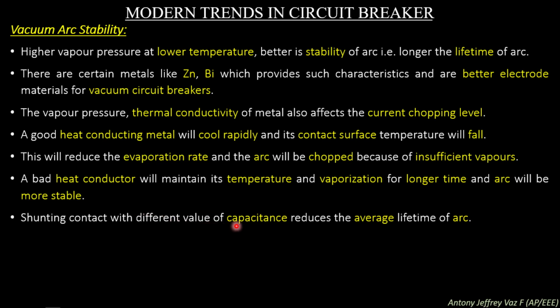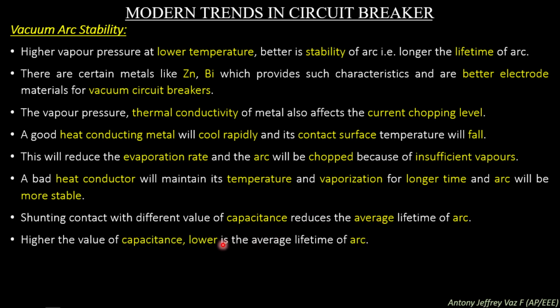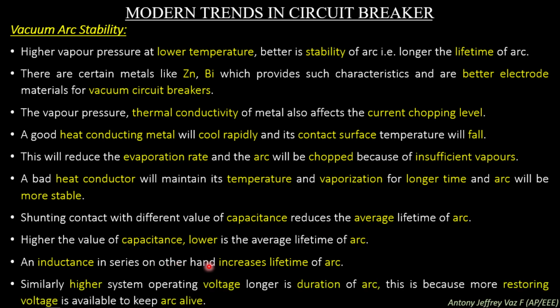Shunting contacts with different values of capacitance reduces the average lifetime of the arc. The higher the value of capacitance, the lower is the average lifetime of the arc. An inductance in series, on the other hand, increases the lifetime of the arc. Similarly, the higher the system operating voltage, the longer is the duration of the arc. This is because more restoring voltage is available to keep the arc alive. So, a vacuum circuit breaker can be designed so that it can be superior in arc extinguishing properties. Thank you.